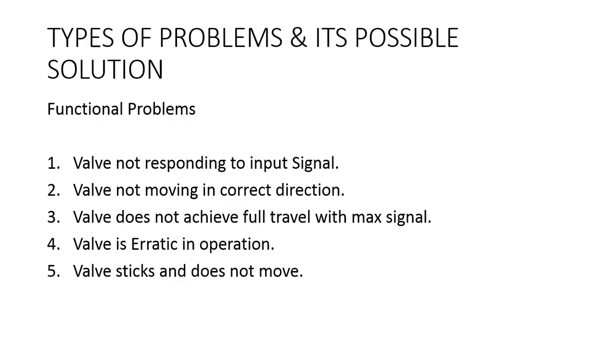If insufficient power is the problem, then assure that sufficient air pressure is available for full stroke of the valve through the available pressure gauge at the AFR inlet. Cross-check with the valve datasheet.